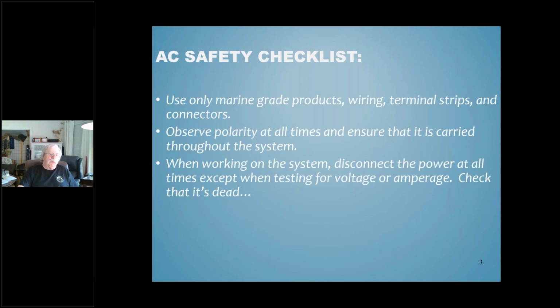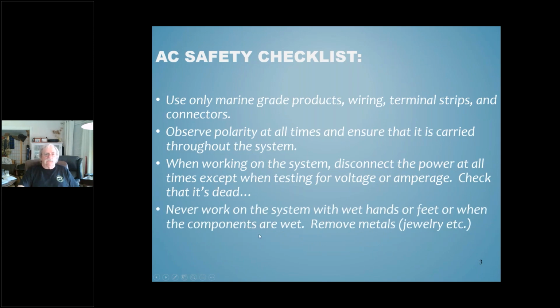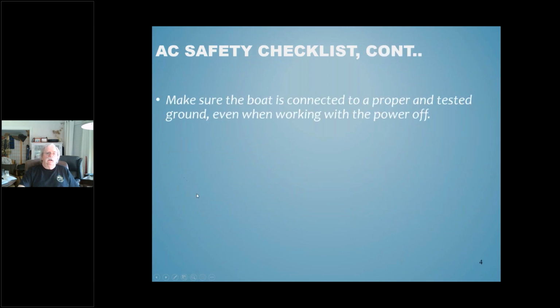It's one of the reasons why we require some indication that there's an inverter on board to be on or near the main panel board. Should be common sense here, but I'll say it anyhow. Never work on the system with wet hands or feet or when the components are wet. Make sure the boat is connected to a proper and tested ground, even when working with the power off. Rubber-soled shoes. Keep the distractions to a minimum.